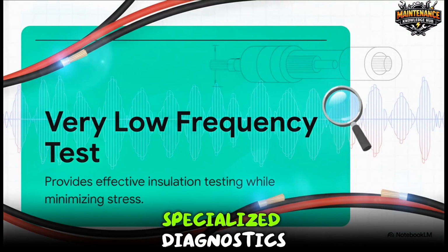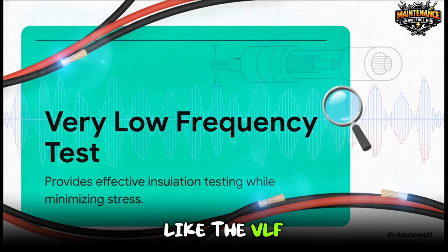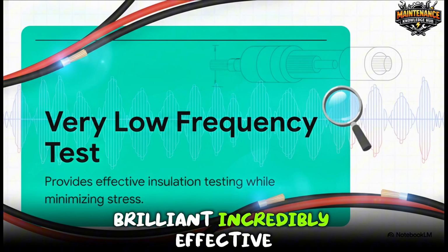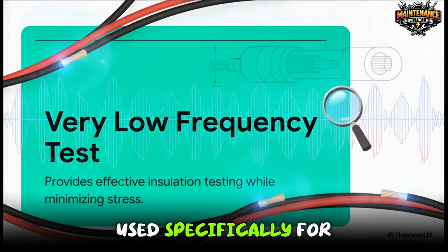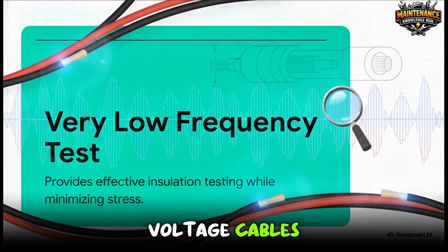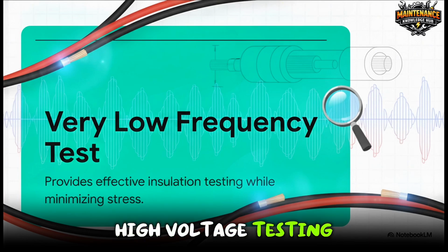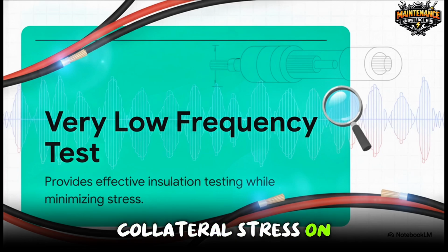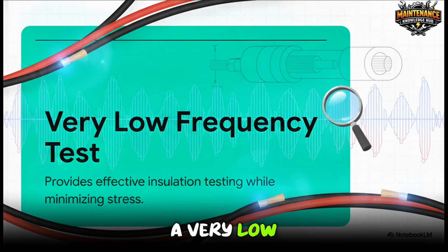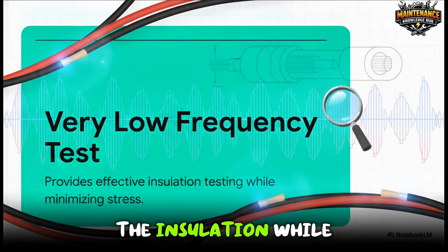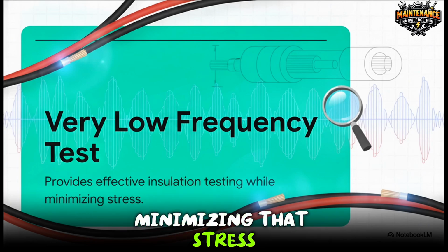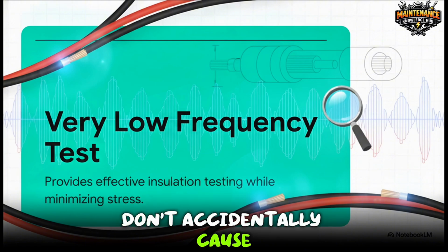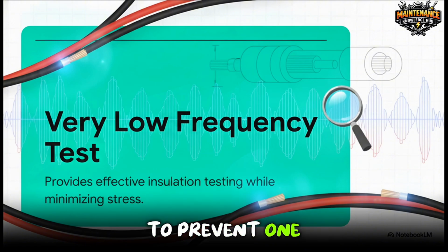Then we get into the more specialized diagnostics, like the VLF, or Very Low Frequency test. This is a brilliant, incredibly effective tool used specifically for medium and high voltage cables. You see, standard high voltage testing on really long cable runs can sometimes put unnecessary collateral stress on the system. But by using a very low frequency, technicians can provide a thorough, rigorous test of the insulation while safely minimizing that stress. It ensures we don't accidentally cause a failure while we're trying to prevent one.